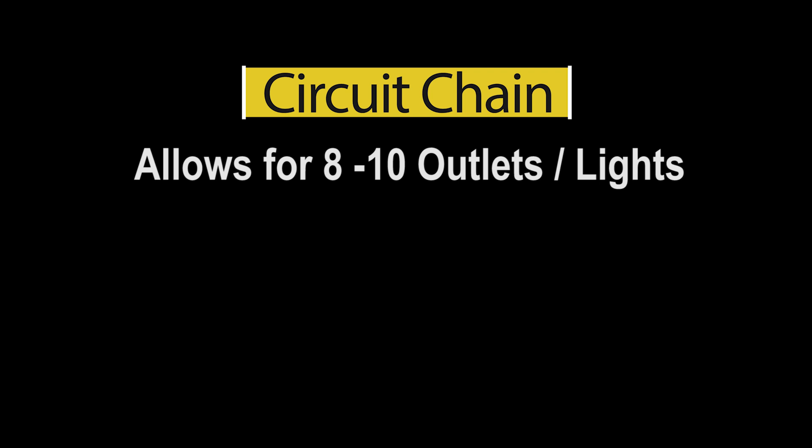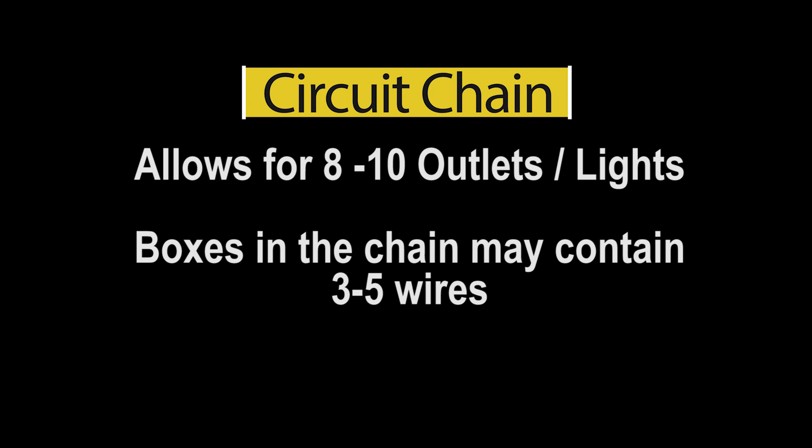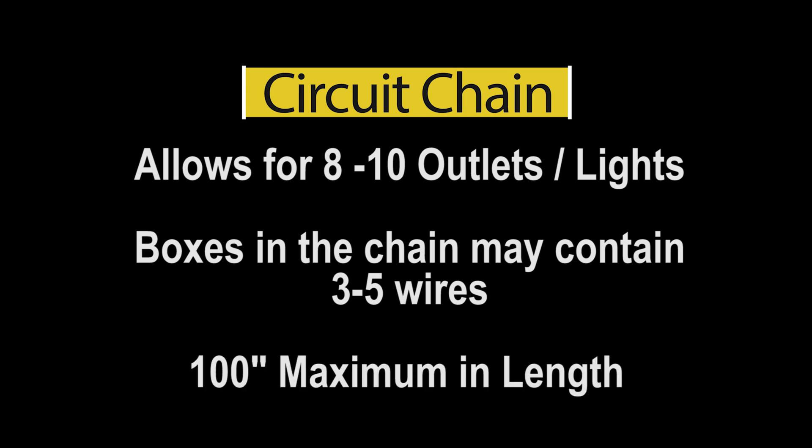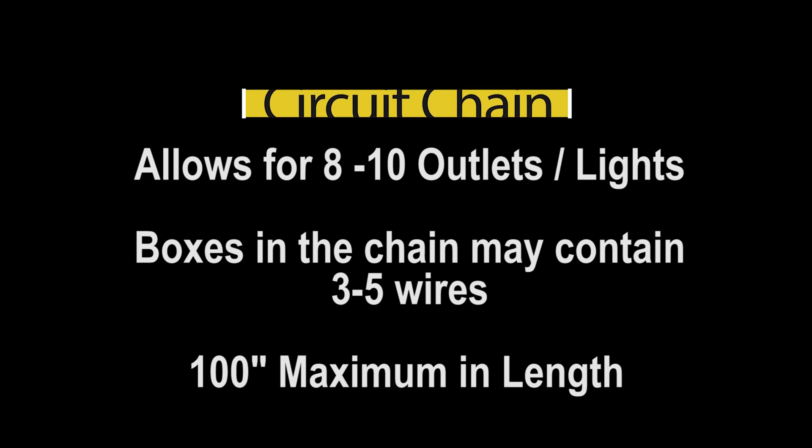Normally, you can put eight to ten outlets and lights on a single circuit breaker connection chain. And throughout this chain, you will have three to five connections in each box, depending on the type of connection. Something else to keep in mind about the GFCI protected circuit is that it should stay under a hundred feet in length. So here is how this power distribution happens, so you can easily identify the type of outlet you opened up.